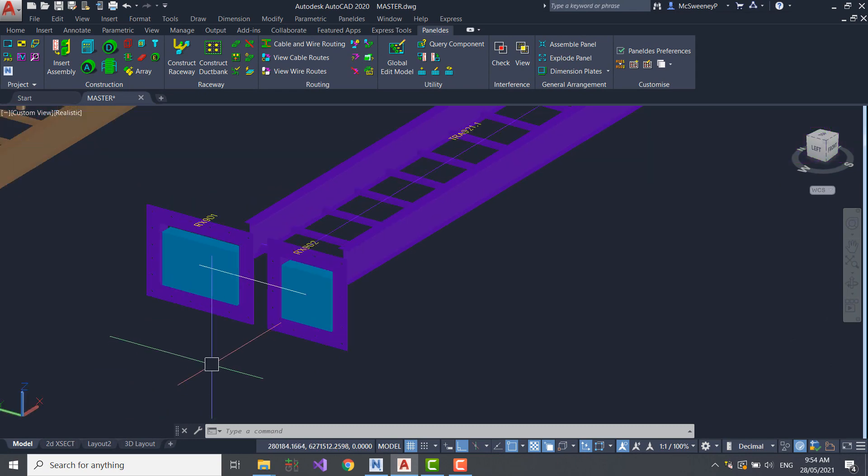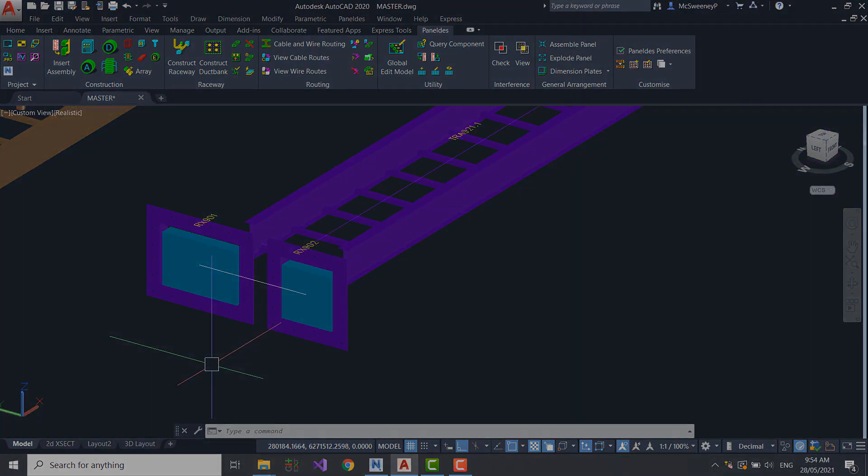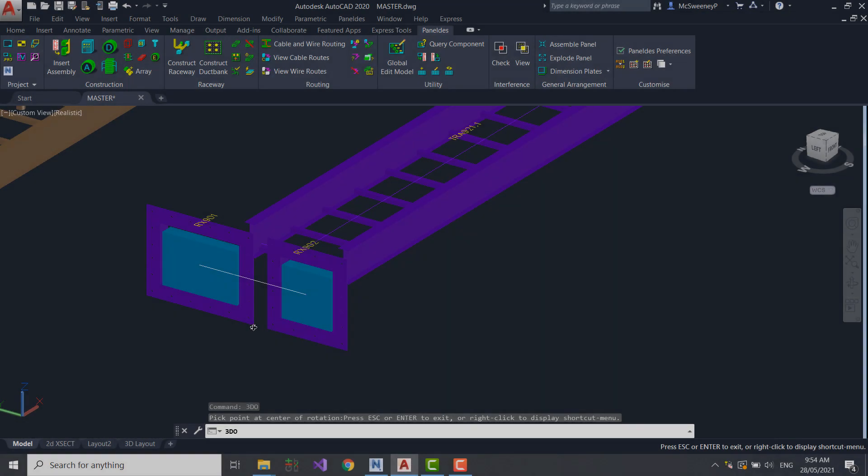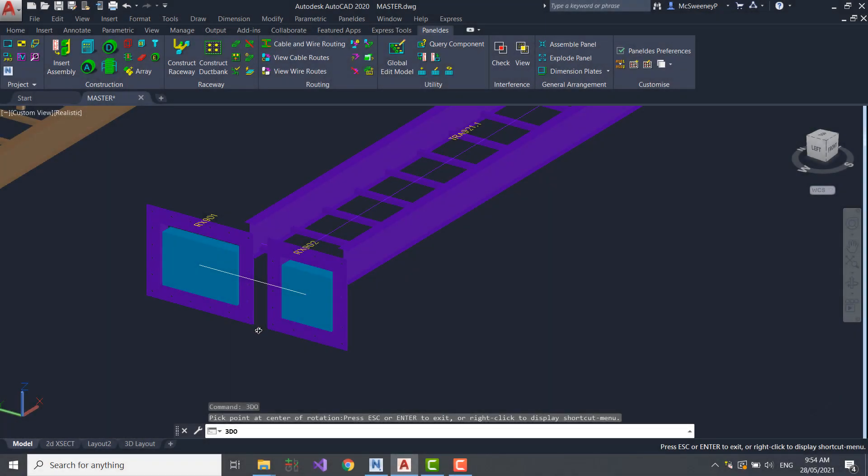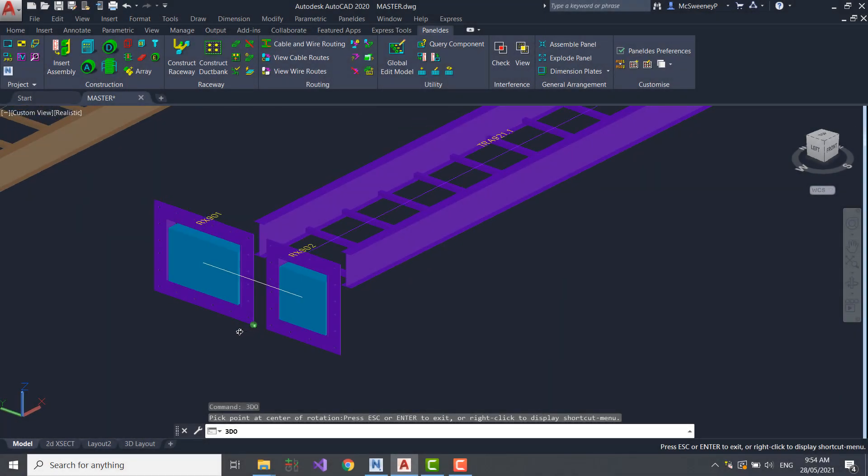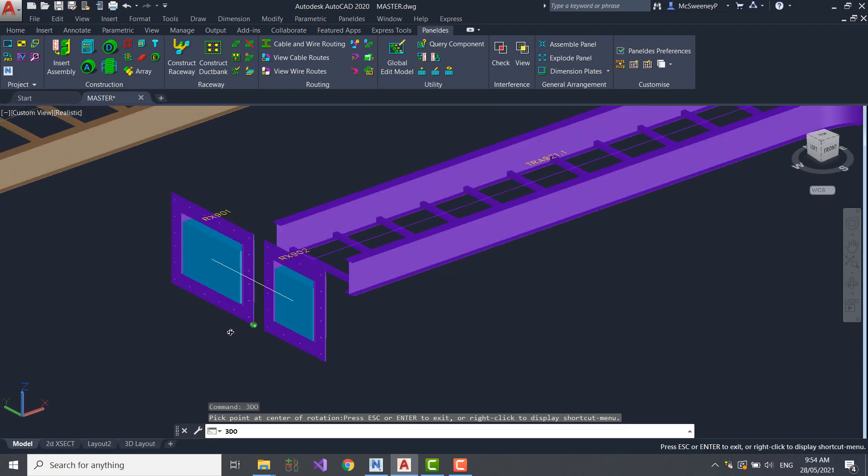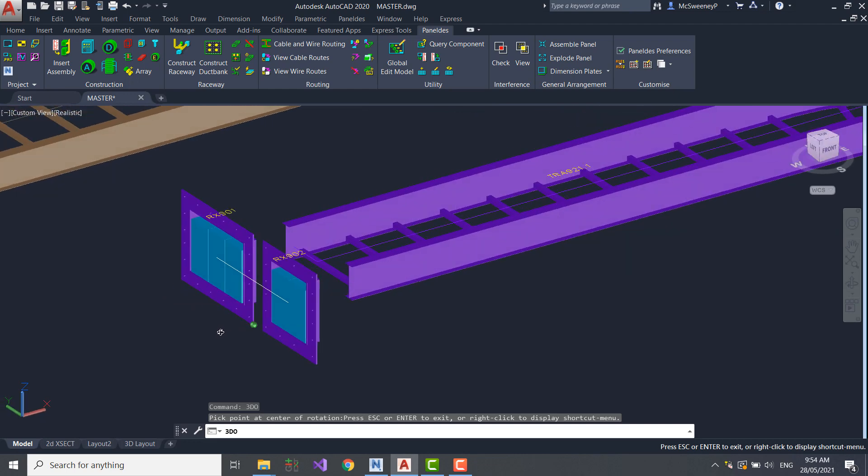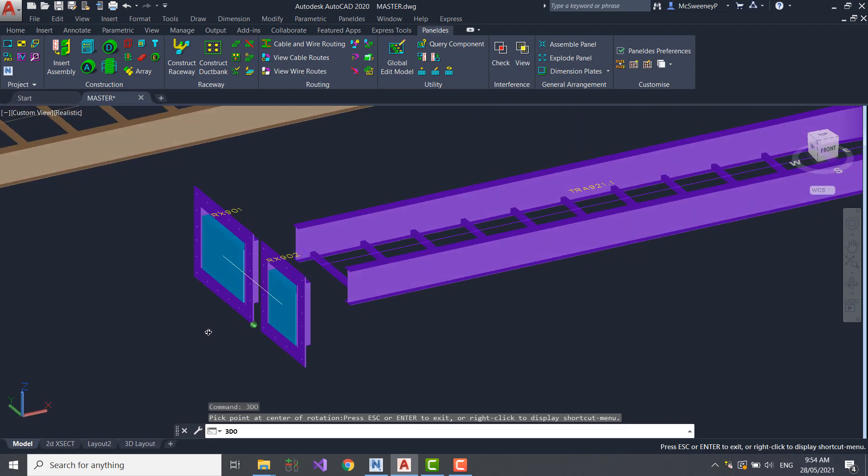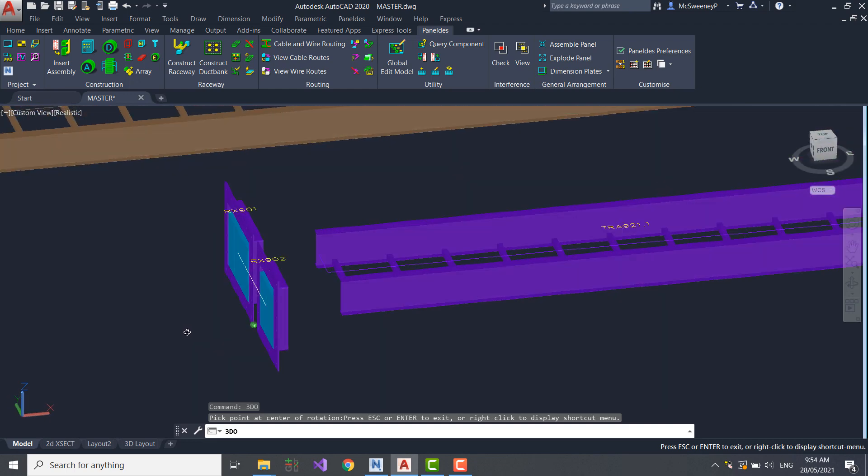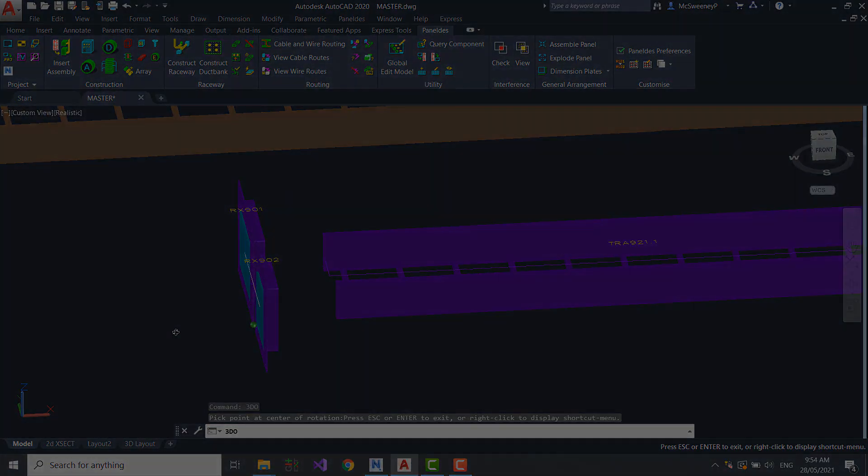Every sealing block understands which cable sizes it can accommodate. Paneldes Raceway can prepare the plan for filling a transit, produce a 2D cross-sectional layout of the plan and a report for all blocks and cables in the plan.